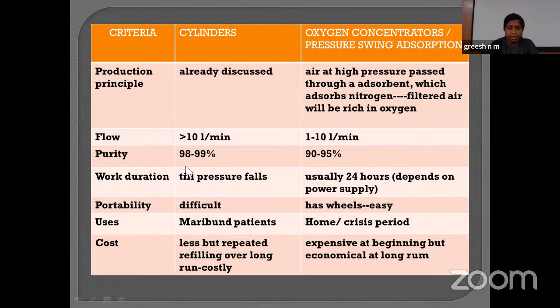Purity of the oxygen will be 98 to 99% with the cylinders, whereas it is 90 to 95% with the concentrators, which is lesser. The work duration with the cylinders is until the pressure falls, whereas with the concentrators it usually is up to 24 hours, but again, it depends upon the power supply because uninterrupted power supply is required for the oxygen concentrator working.